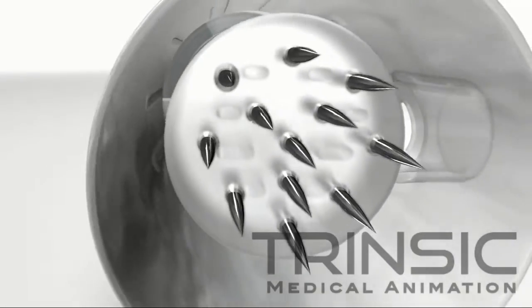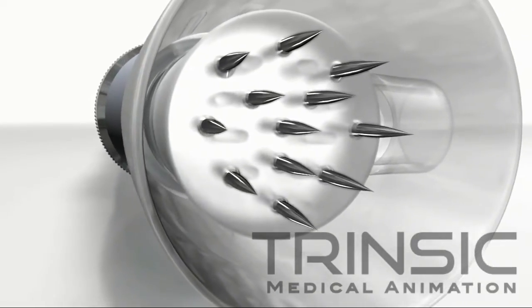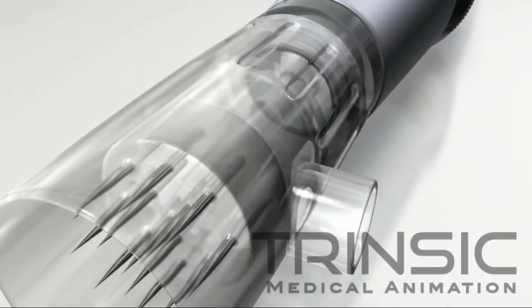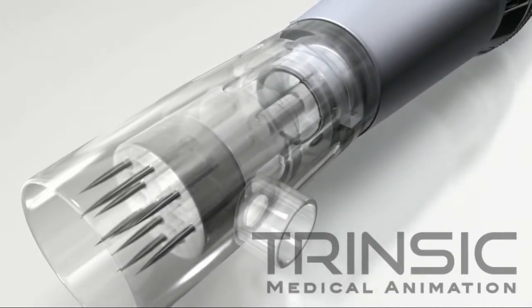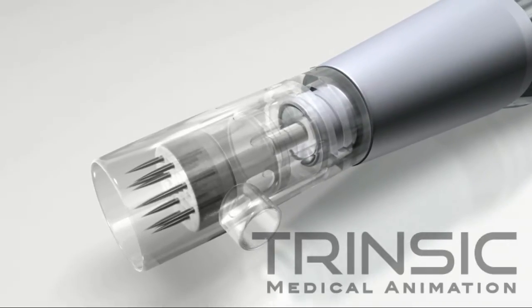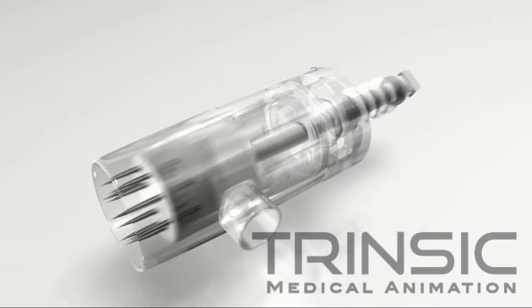Micropen's turbo safety needle consists of 12 32-gauge medical-grade needles arranged in a fractionated pattern in order to cause the necessary mechanical injuries to the skin while leaving healthy skin intact between each microperforation. The turbo safety piston pulsates at a rate of 8500 RPM to ensure optimal patient comfort.